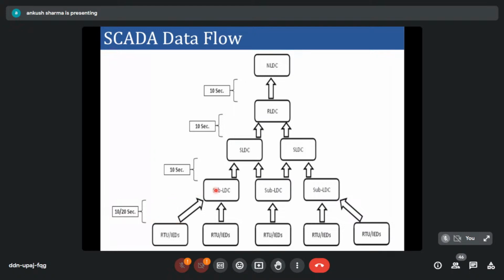Now, in each data communication step you add some delay. From RTU to sub LDC you may add about 10 seconds, then sub LDC to SLDC another 10 seconds, then RLDC, and then NLDC. So across the complete chain, the measurement reaching NLDC is delayed by about 50 seconds to 1 minute. The operation of the power system can go from a healthy state to a collapse state in only 3 to 4 seconds.